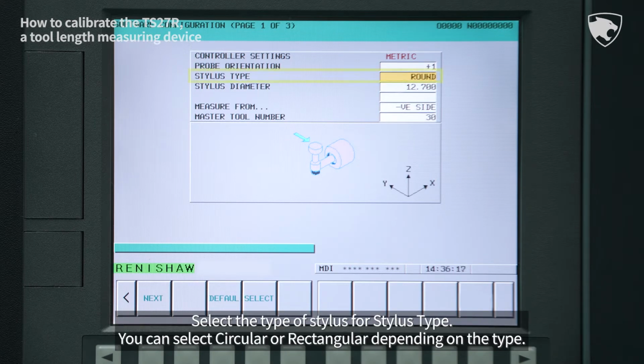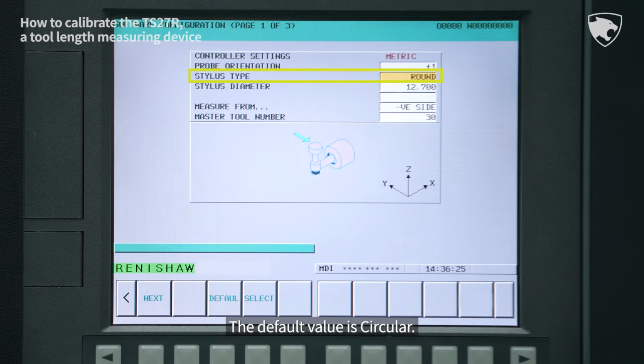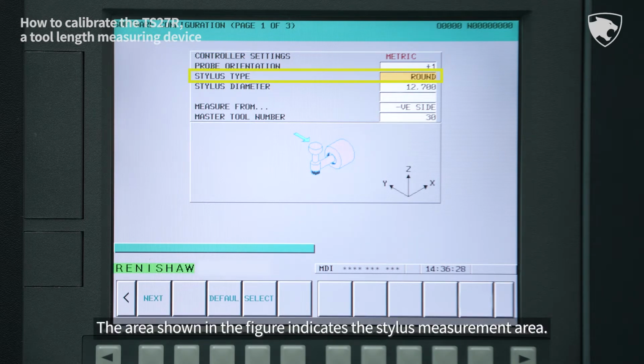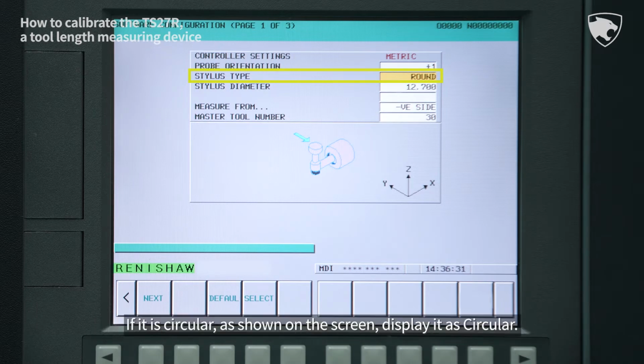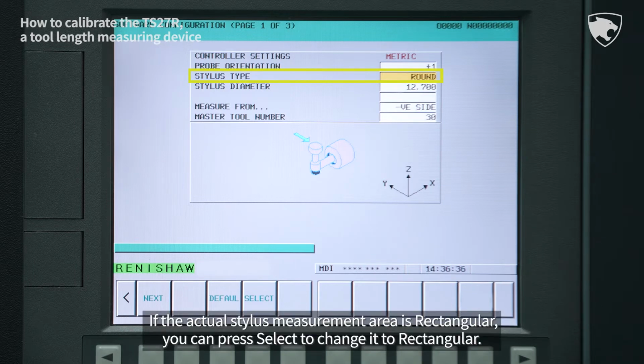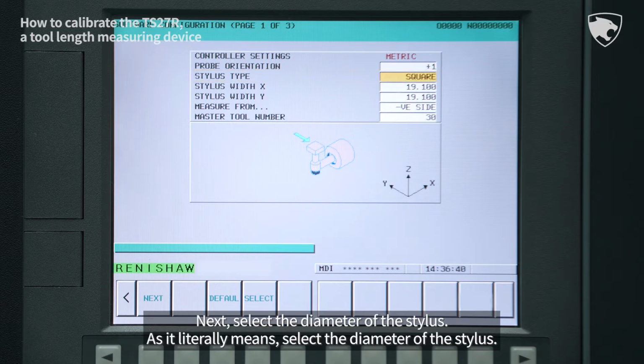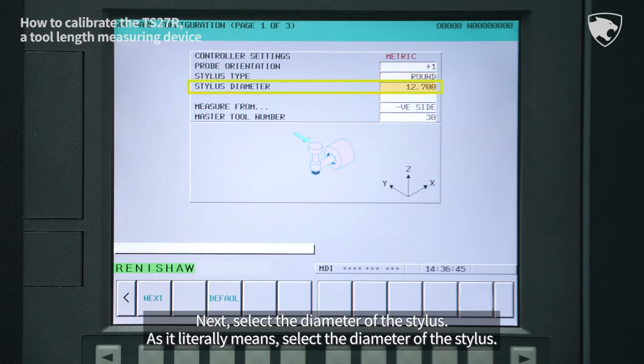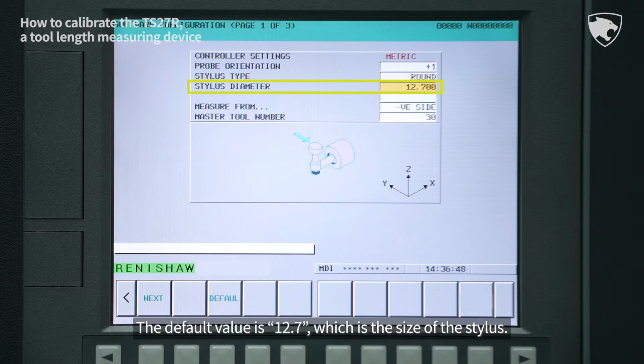Select the type of stylus. For stylus type, you can select circular or rectangular depending on the type. The default value is circular. The area shown in the figure indicates the stylus measurement area. If it is circular as shown on the screen, display it as circular. If the actual stylus measurement area is rectangular, you can press Select to change it to rectangular. Next, select the diameter of the stylus. The default value is 12.7, which is the size of the stylus.